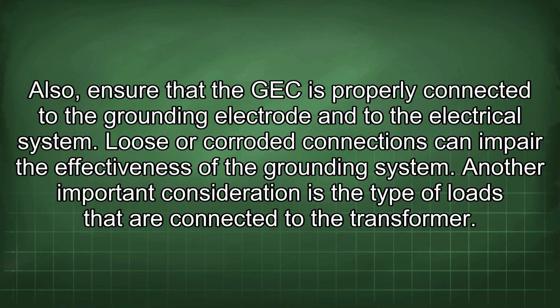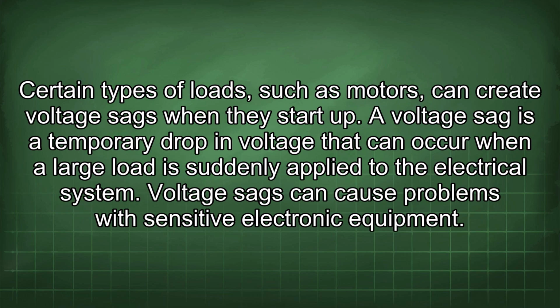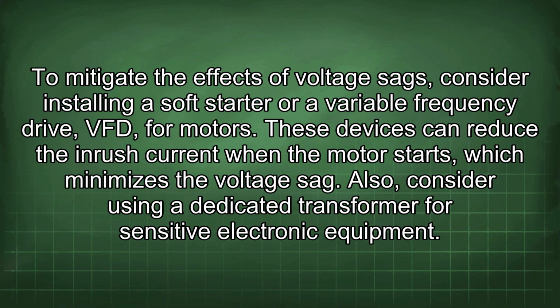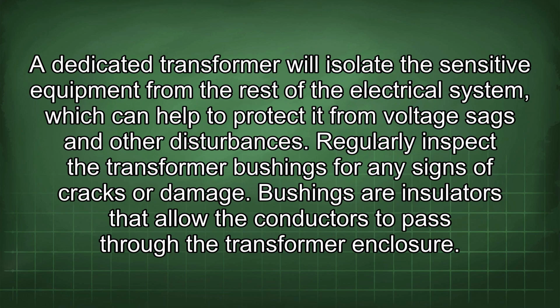Another important consideration is the type of loads that are connected to the transformer. Certain types of loads, such as motors, can create voltage sags when they start up. A voltage sag is a temporary drop in voltage that can occur when a large load is suddenly applied to the electrical system. Voltage sags can cause problems with sensitive electronic equipment. To mitigate the effects of voltage sags, consider installing a soft starter or a variable frequency drive (VFD) for motors. These devices can reduce the inrush current when the motor starts, which minimizes the voltage sag. Also, consider using a dedicated transformer for sensitive electronic equipment. A dedicated transformer will isolate the sensitive equipment from the rest of the electrical system, which can help to protect it from voltage sags and other disturbances.